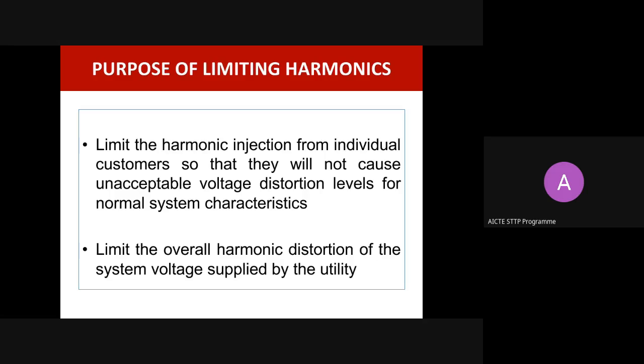For the purpose of limiting the harmonics, we limit the harmonic injection from individual customers so that they will not cause unacceptable voltage distortion levels for the normal system characteristics. So the harmonic injection by the individual customer has an impact on the voltage reaching unacceptable levels.